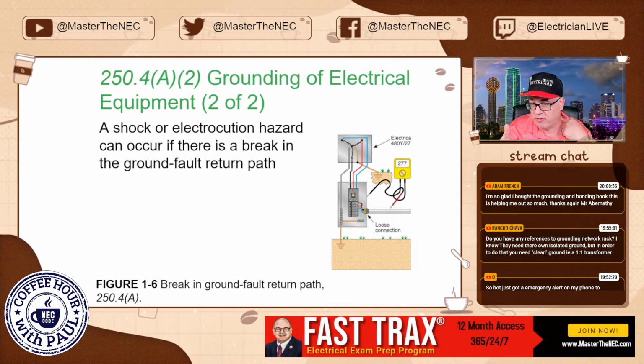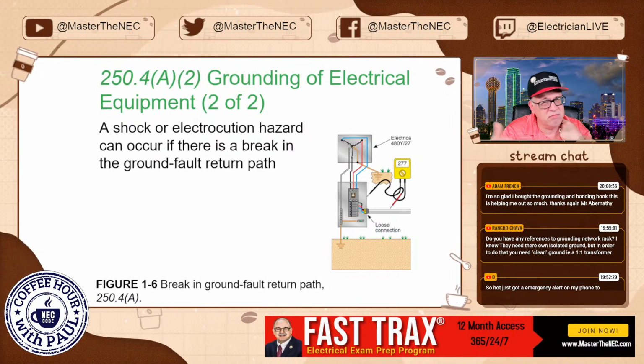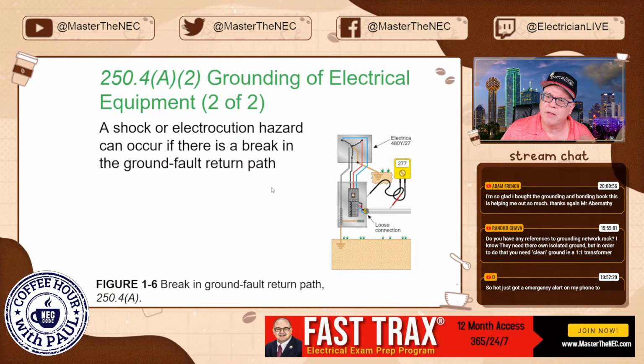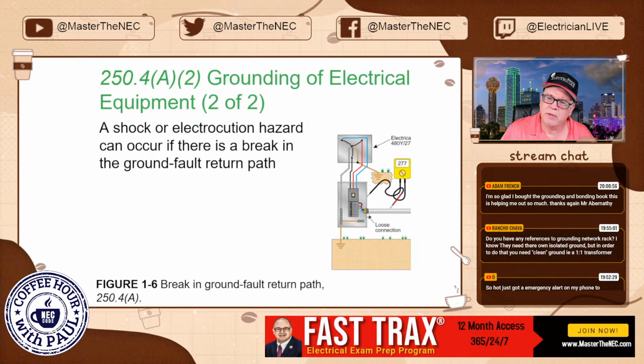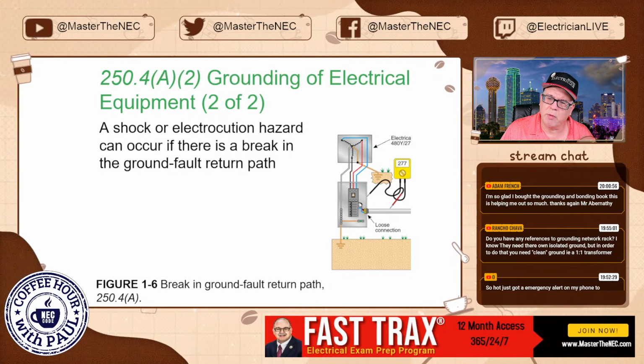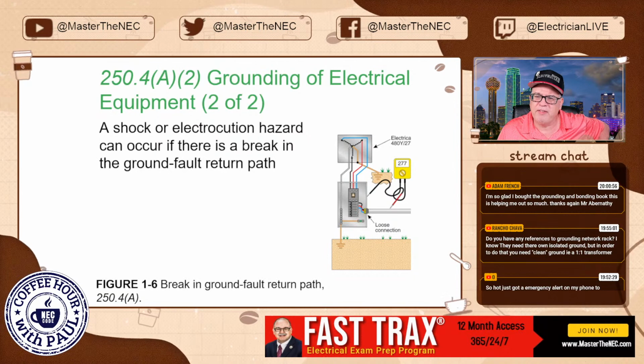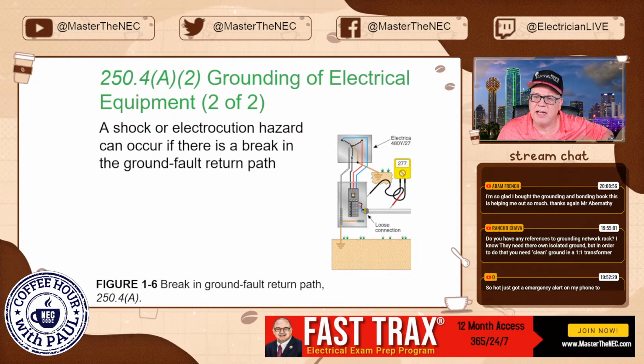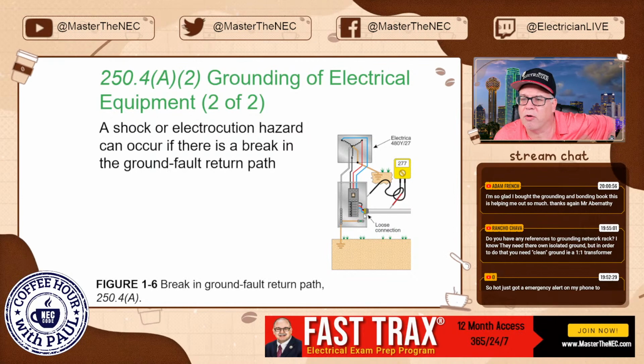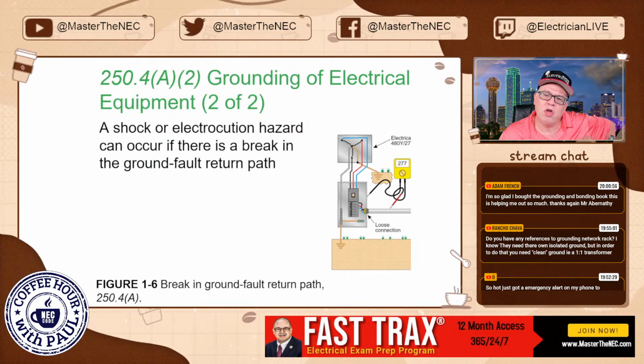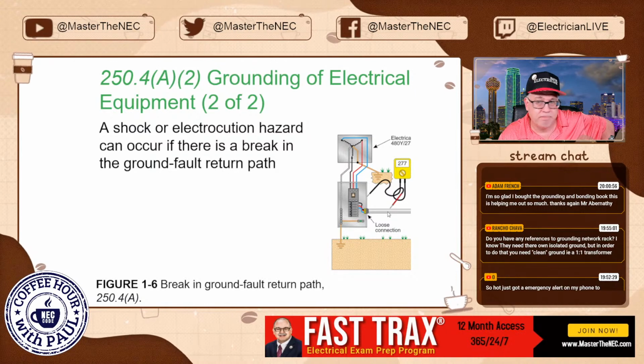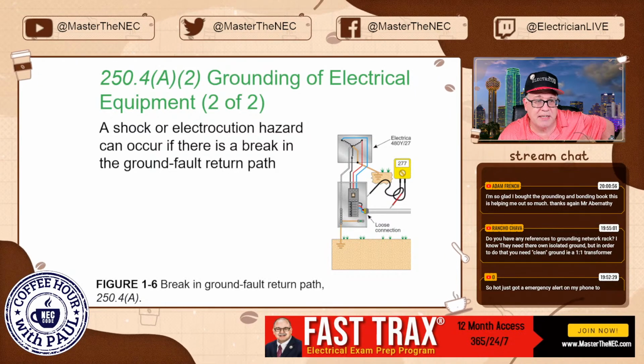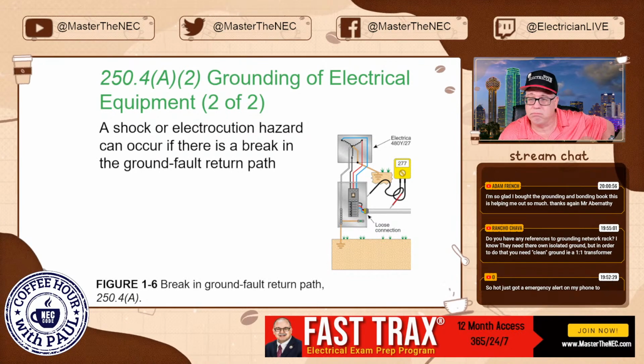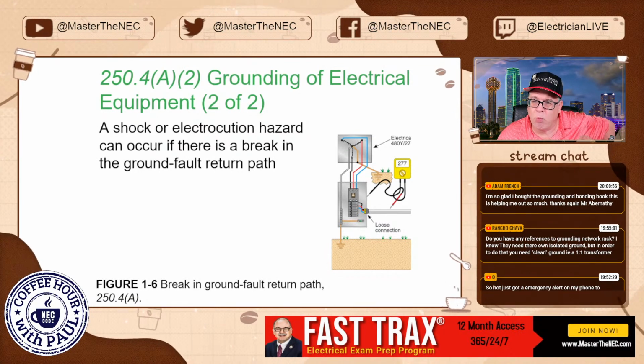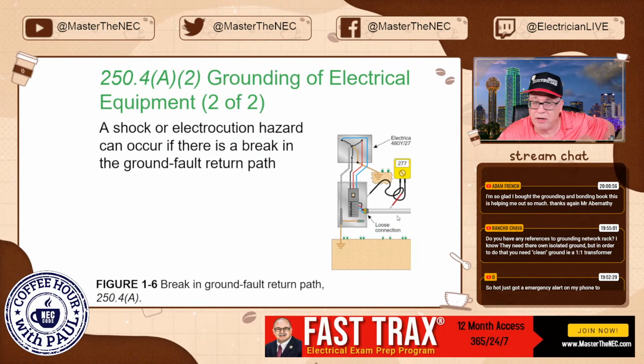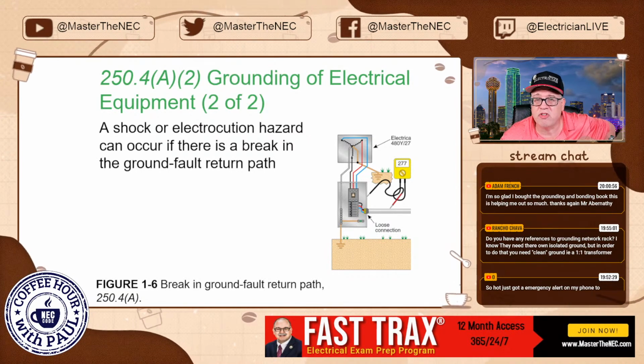You're only as good as your last lock nut. You know what I'm saying? So if you look here, here's a 480/277 volt system, and it looks like branch circuits going out. There's a fault on this end. Now, they're using the EMT. I'm going to assume this is EMT, although I don't see a connector, so it's probably rigid. But it's using it as the equipment grounding conductor. Well, 250.118 says it's okay to do it, so I'll do it. So they didn't run a wire type equipment ground in there. I know some people will cringe at that, but code says you can.